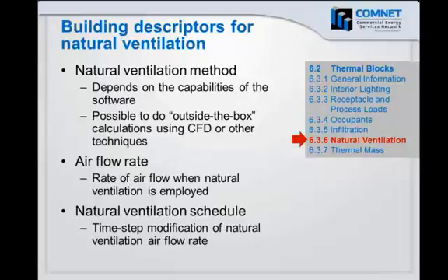What I suspect most people will be doing for natural ventilation is some type of outside-the-box calculation using CFD, or computational fluid dynamics, and then making an input to the airflow rate or a schedule for airflow rates that show what the ventilation rate is when the windows or the ventilation apertures are open and when they're closed, and then this would be modified by a schedule. I've had some success modeling natural ventilation in this manner.